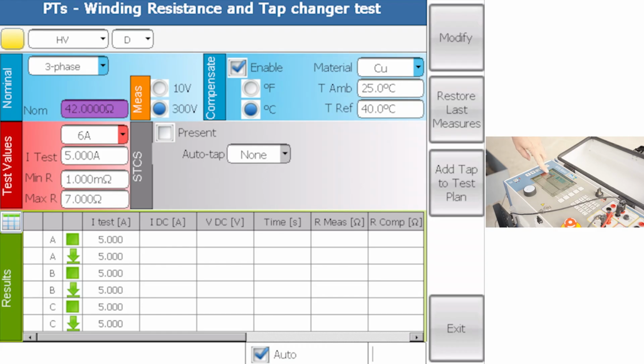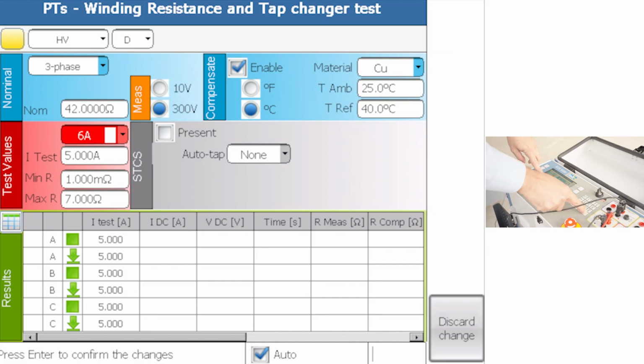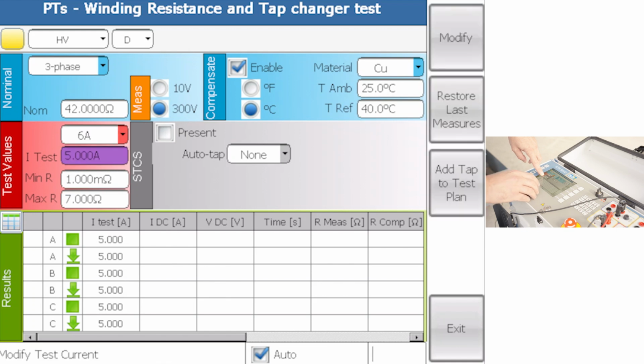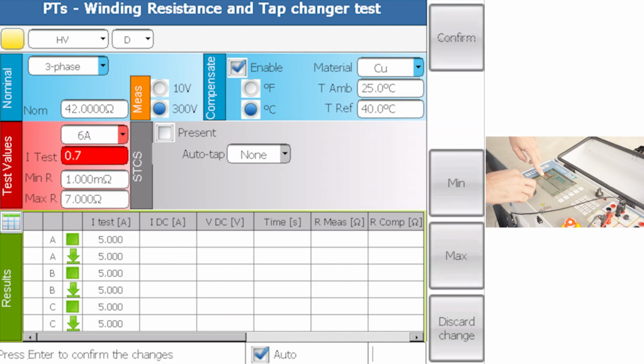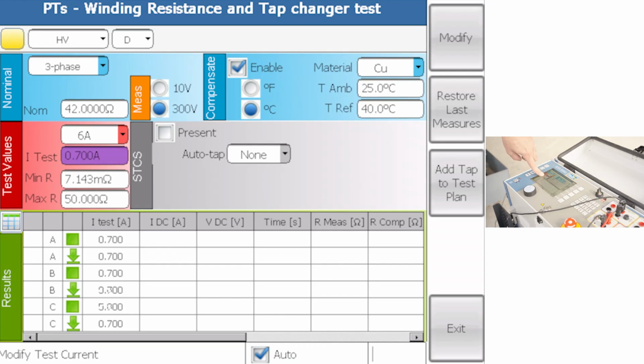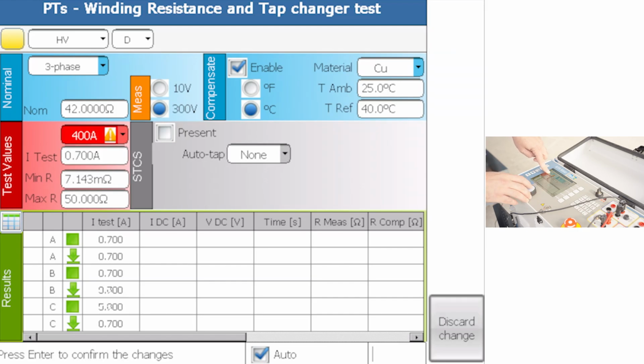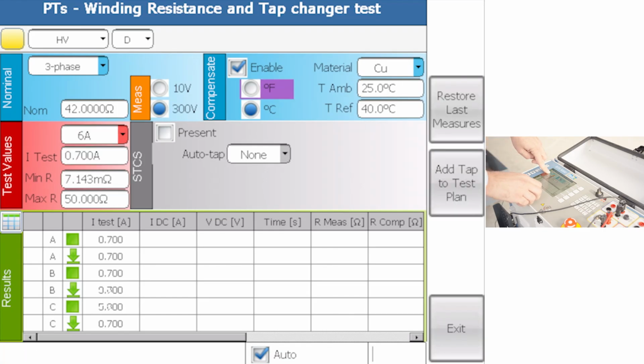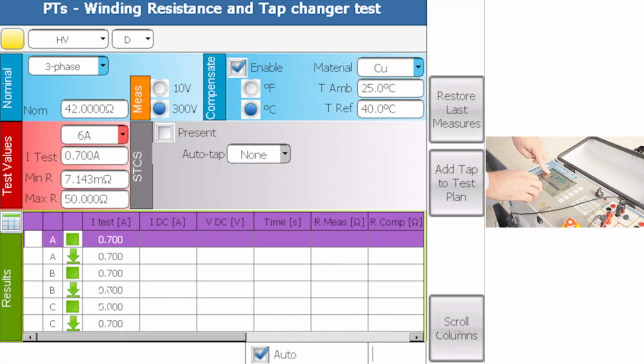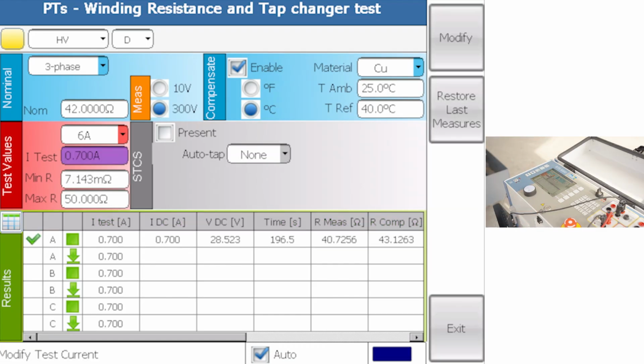42 ohms. I cannot measure it with 5 amps because the maximum resistance I can measure with 5 amps is 7 ohms. So I'm going to change this to 0.7. And that allows me to measure resistances up to 50 ohms. Let me just repeat and show you that you could also use the output 400 amps, but in this case I prefer to use the 6 amp output. I'm connected between phases A and B, and I press start. Okay, so we finished with phase A.